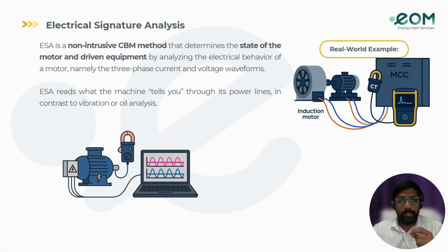Let's start with the fifth technique of CBM, which is electrical signature analysis, ESA. ESA is a non-intrusive CBM method that determines the state of the motor and driven equipment by analyzing the electrical behavior of the motor, namely the three-phase current and the voltage forms as well. ESA reads what the machine tells you through its power lines, in contrast to vibration and oil analysis.